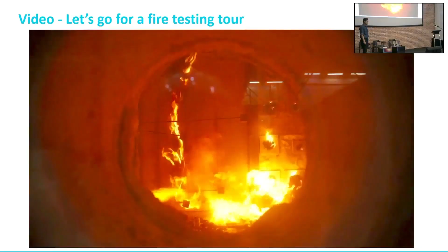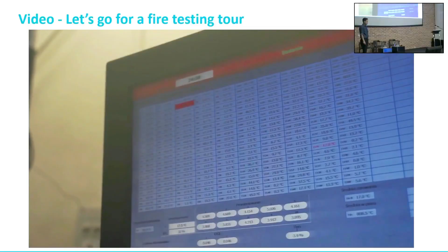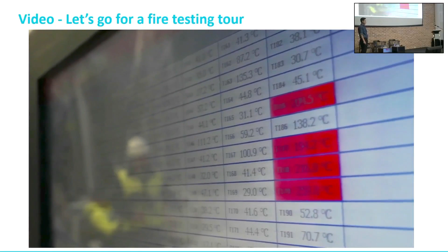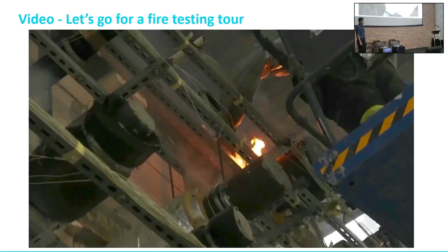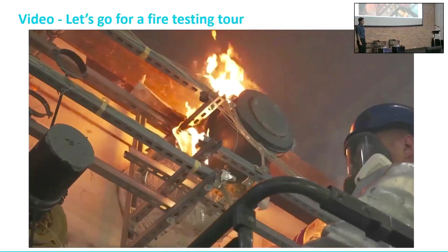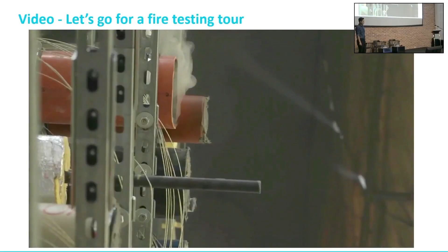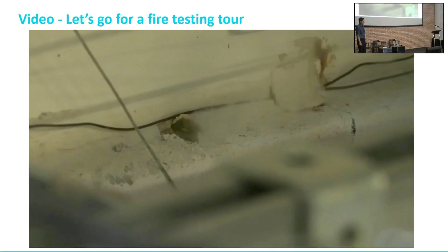The temperature of the furnace at 90 minutes reaches more than 1000 degrees Celsius. The thermocouple's reading can be checked at any time during the test on the monitor screen. It shows the fire resistance and insulation, that is, the ability of an element to withstand the effects of fire from the exposed side to the unexposed side. We test the fire tightness with the help of a gap gauge, a cotton pad, or optically. This property is considered to be lost when a continuous fire of more than 10 seconds occurs on the unexposed side of the test specimen, or the cotton pad catches fire within 30 seconds of being applied to the test specimen, or when the fire results in a gap exceeding the permissible dimensions.